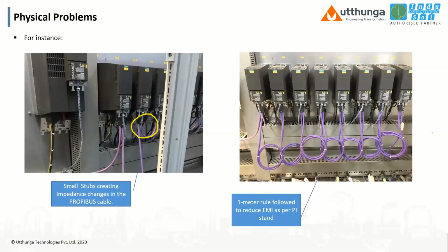This is the second case. You can see the left side image. Drives are connected using small stubs, with more than 10 or 15 of them. They connected the drives using small stubs and had huge intermittent failures, like weekly. The drives were going off and suddenly restarting. Then what do the maintenance guys do? They go and restart the controller. Then the system starts working again.